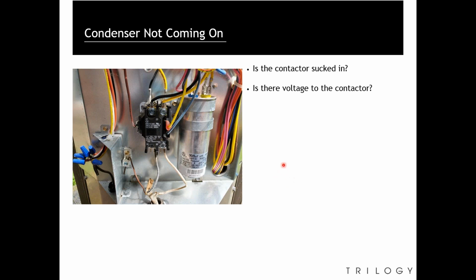If we need to test using a voltage meter on VAC, check the yellow and red thermostat wires for 24 volts. Is there voltage to the contactor? We need to have 120 volts on the black and the white leg with a total of 240 volts to run the condenser. So make sure the breaker on the inside is on.